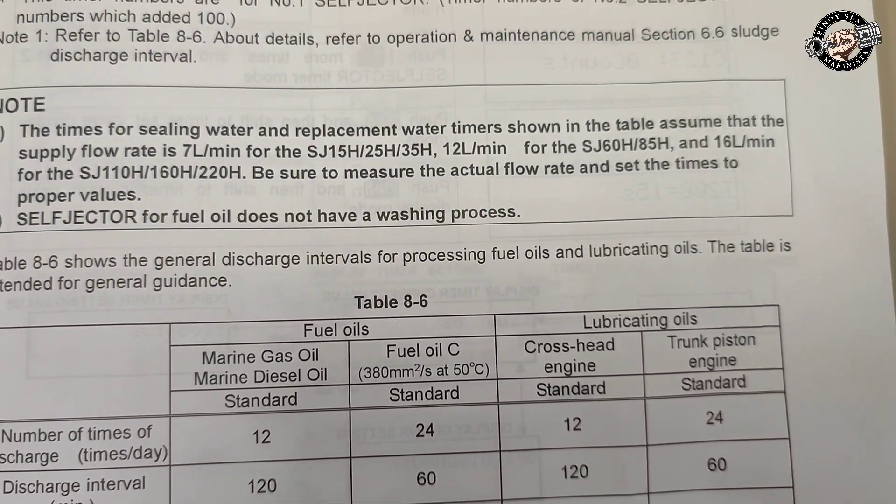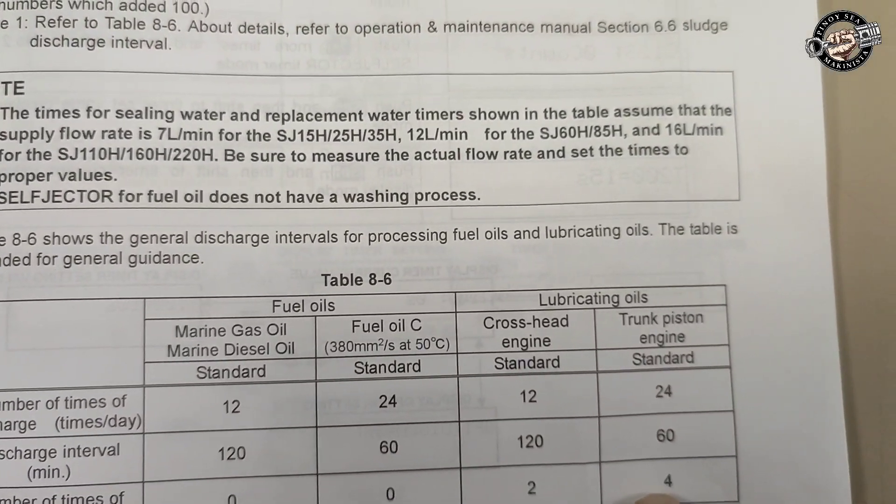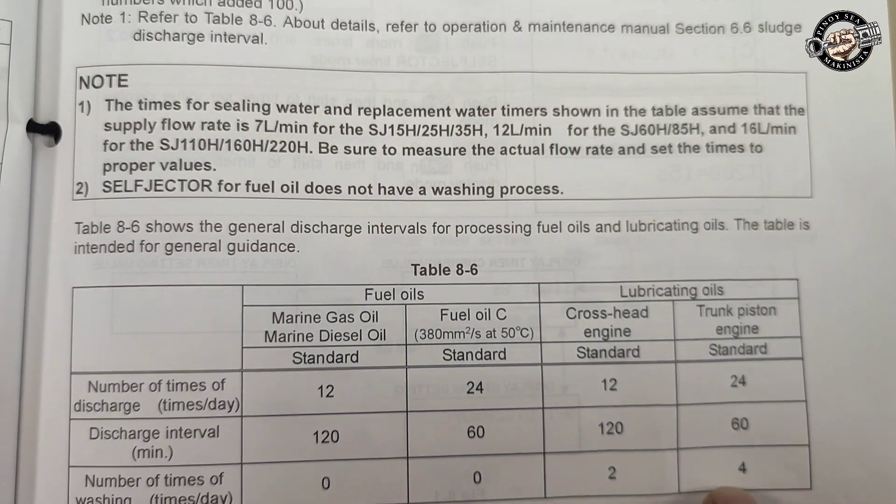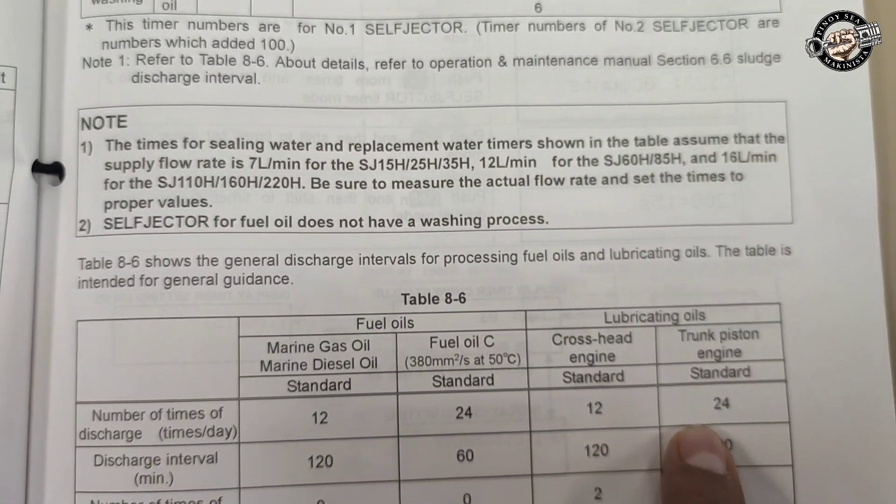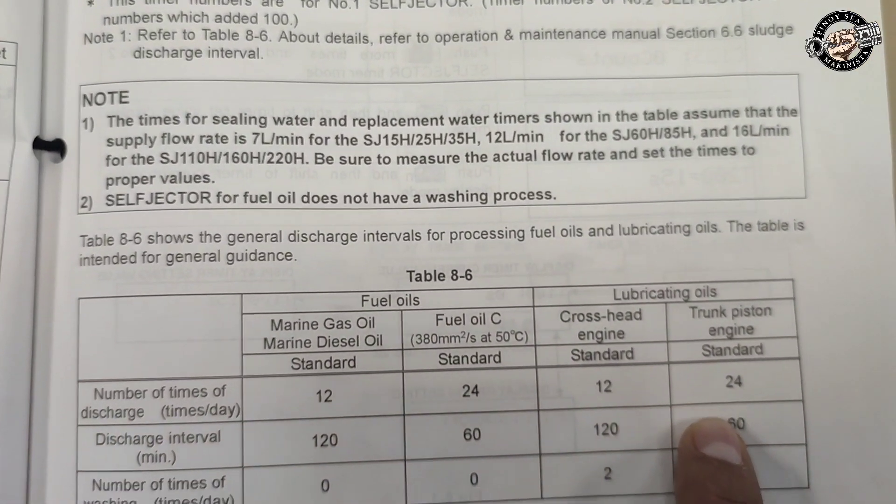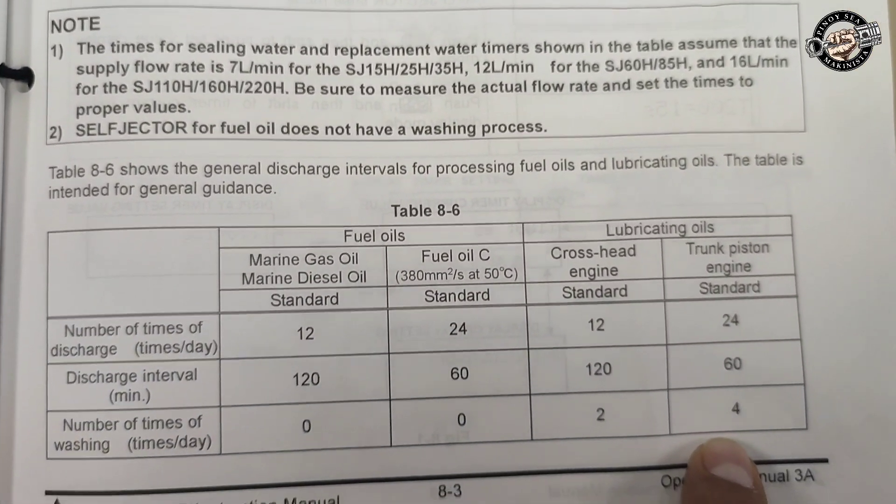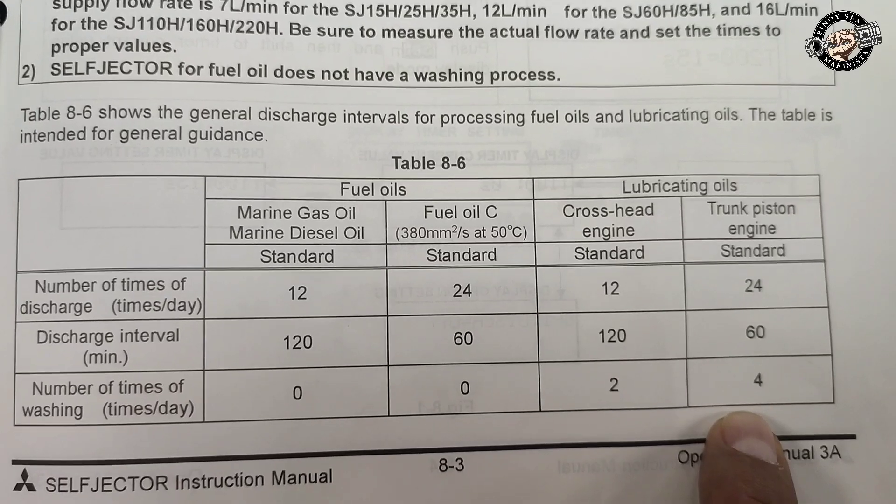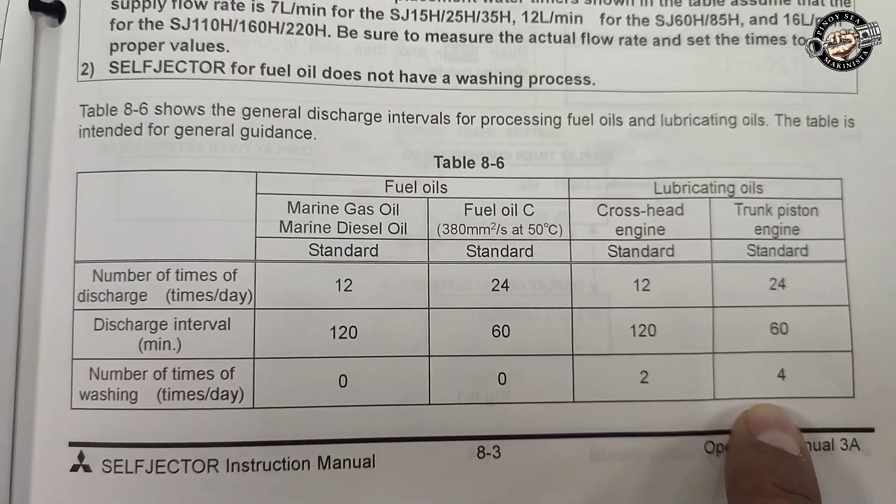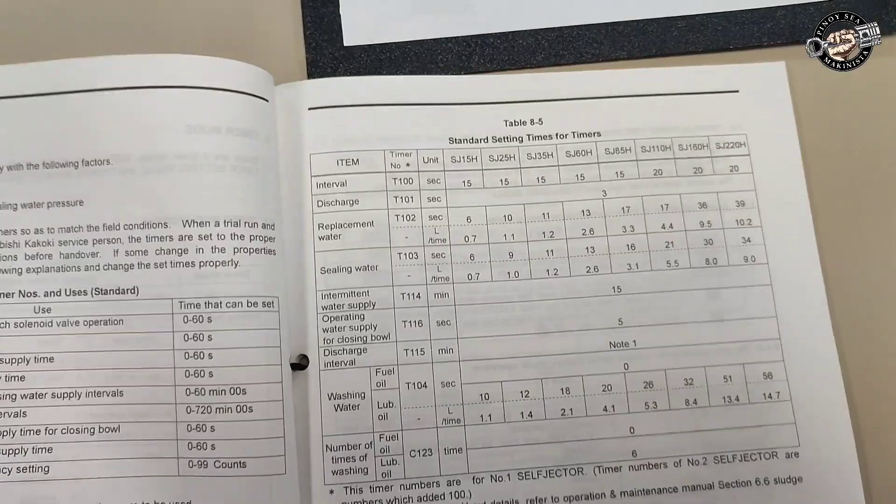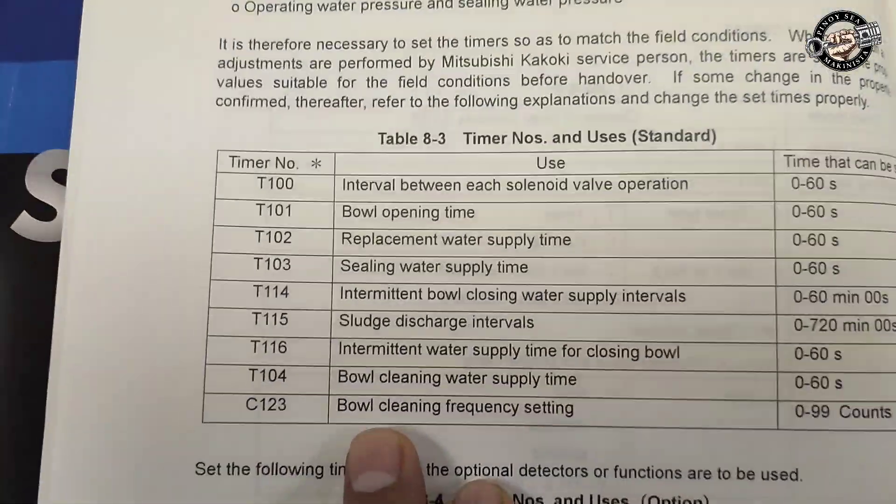The sludge discharge interval is 120 minutes or every two hours, or depending on the quality of your lubricating oils you can make it 24 times per day or every hour. Now we will select the timer that we are going to change the set value—that T115 sludge discharge interval.